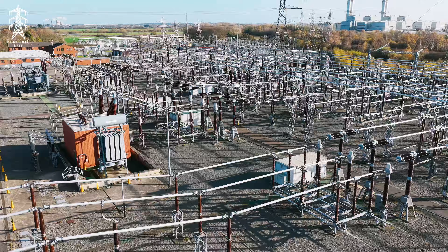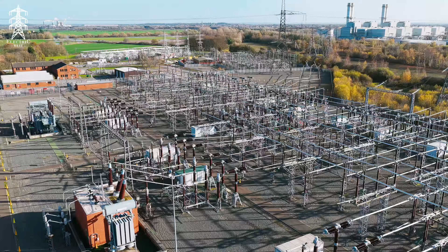But the alternative is this could actually be a bus duct, where essentially it's your normal air insulated bus bar. So when you see a substation, it's usually air insulated, where everything's exposed outside. You see either the thin copper bars or the big thick aluminium bars, and that transports the electricity. But with air insulated, we space them out quite far, because you need a bigger gap, because the insulating medium is just air. The only thing stopping one bar from arcing to the other, phase to phase, is the air. The air provides that insulation for the electricity. And again, I've got a whole video coming on the way electricity arcs through the air, and how things like air temperature and moisture affect that.